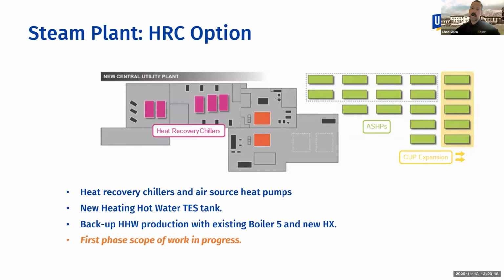And the heating hot water TES system combined with heat pump technology is expected to increase the plant efficiency to a COP over 5. So our plan is to also keep 1 or 2 of the natural gas fired steam boilers coupled with a steam to hot water heat exchanger as a backup source of hot water. So it's good to hear that recommendation earlier as part of maintaining reliability because we were intending to do that also. Also makes sense to plan to utilize it if you're going to pay standby tariffs for your rate, which I don't even know what a SoCal gas standby tariff looks like, and I wasn't able to get that from anybody.